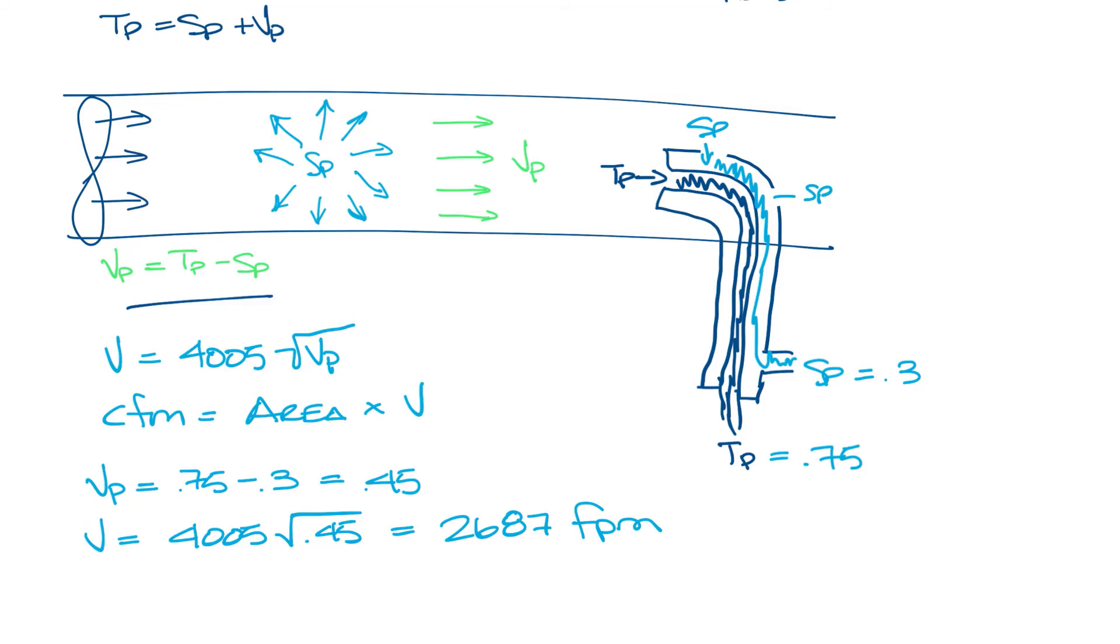Now let's say this is an 8 inch round duct here, so we can calculate the area. So the area of an 8 inch round duct is pi r squared, which equals 50.26 square inches, and we need to convert that to feet. So divide that by 144, and we get 0.35 square feet.